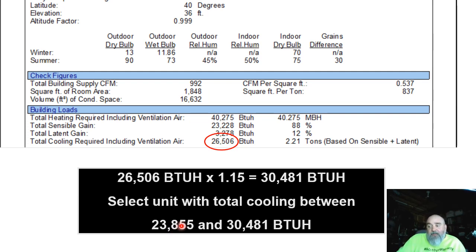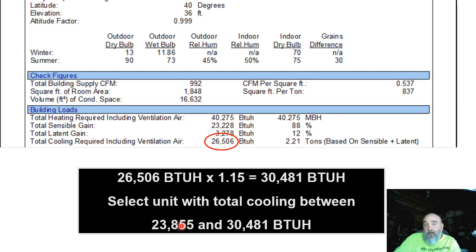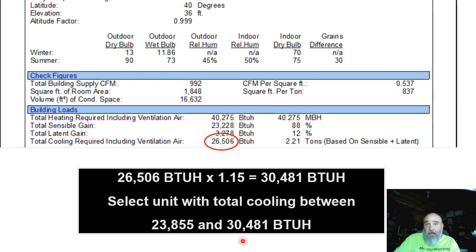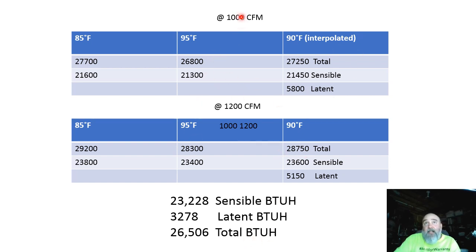There's potential to struggle on design days, but as long as your customer is fine with it, that's acceptable — and I think they're going to be happy more of the time if we follow this guidance than if we install oversized equipment. Yes, Manual S does talk about 20–30% oversizing, but that applies to two-stage and variable-volume equipment. Never let the phrase 'it's okay, I oversized it — I'm putting in multi-stage equipment' come out of your mouth, because you're not following good design practices.